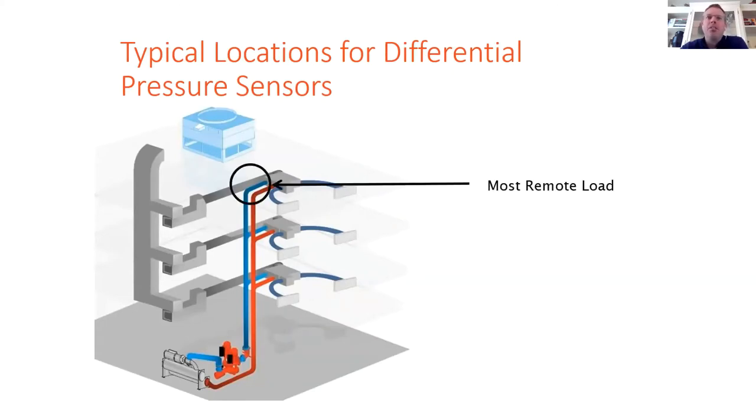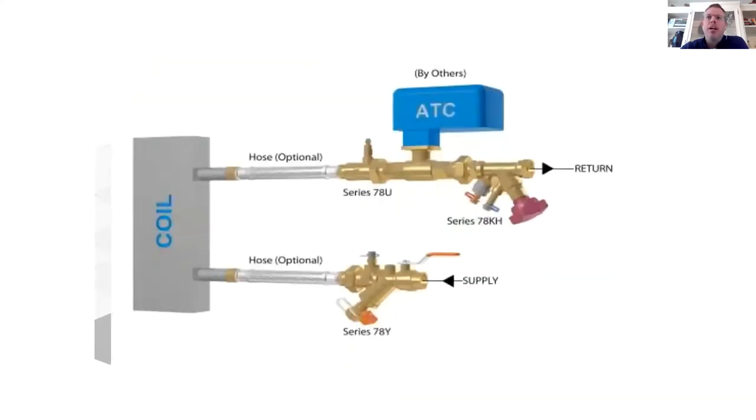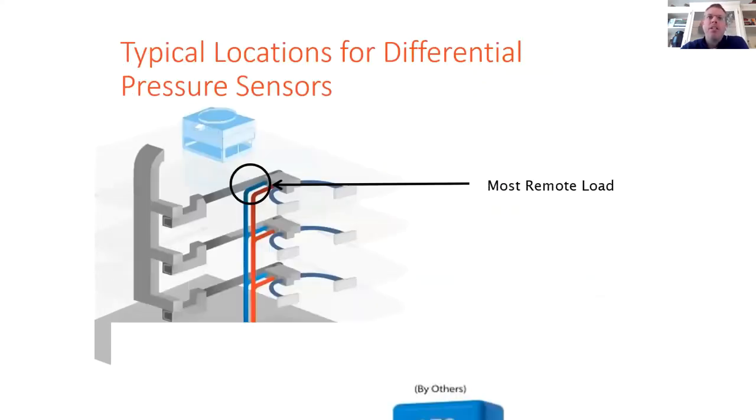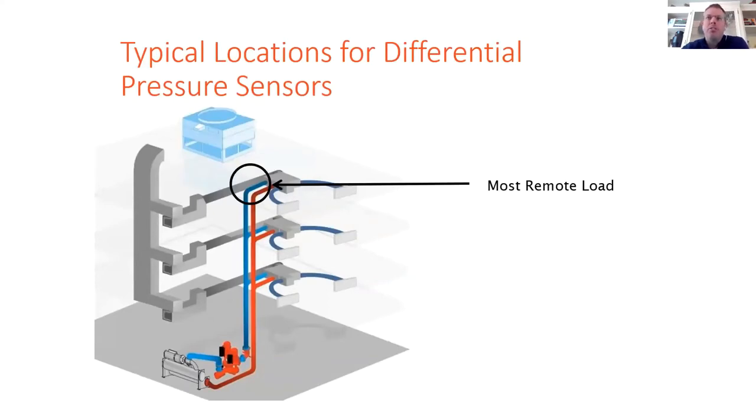The location of the differential pressure sensor is actually critical to the amount of energy that can be saved at the pump. The first and most ideal location is at the most remote load. So this is the load with the longest run of piping where the fluid is going to experience the most pressure drop before reaching the load. And the set point is typically the pressure drop needed to overcome the control valve, the strainer, the balancing valve, the coil, et cetera, and a short run of piping. This allows your minimum head set point to be low in comparison to the full flow head pressure set point and allows a great deal of pump turndown.